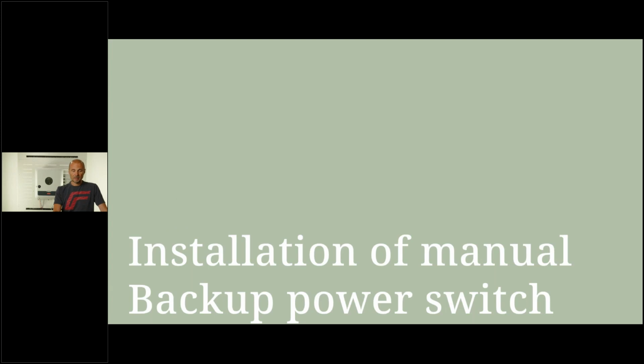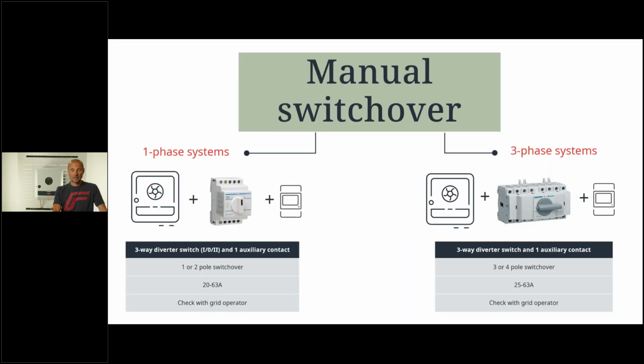Now, if we come to the manual backup power switch, so the full backup solution, but now with the manual switch, we also have two solutions, for single-phase systems or three-phase systems. You need this switch, a 1 or 2 pole switch over, 20 to 63 amps depending on the power you need, or the 3 or 4 pole switch over with 25 to 63 amps with an auxiliary contact. Additionally, on both, you need to get the feedback to the inverter that the switch is in off position. You always need a switch with 3 positions: position grid, position 0 off, and then a position off grid power or full backup.